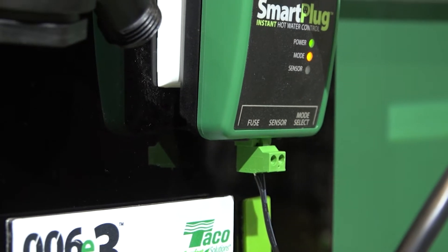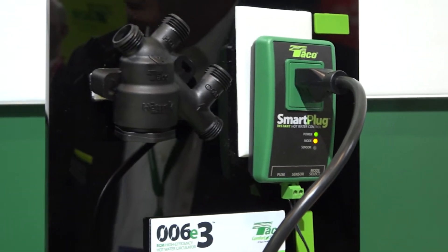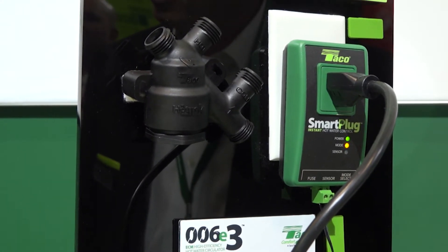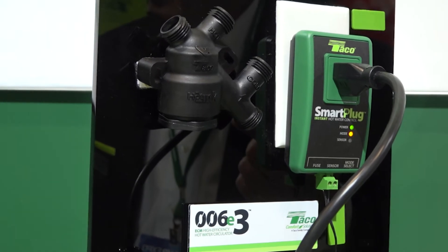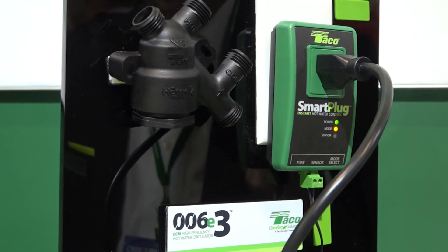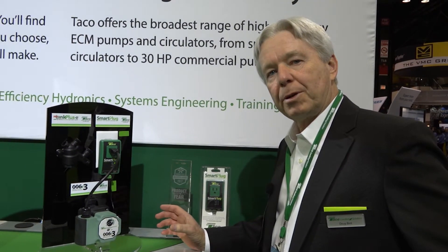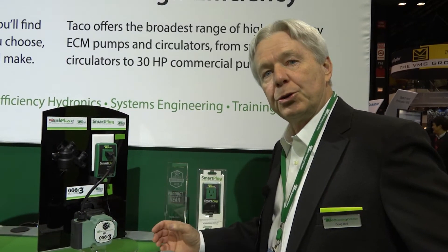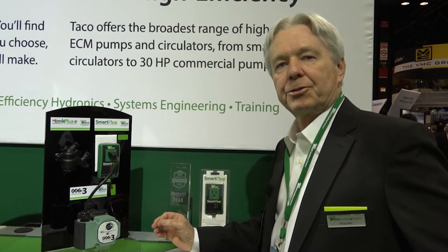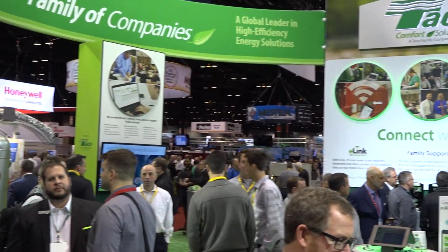Now the mode is set to solid yellow, which tells us it's in learn mode. Through the sensor, it's learning exactly when the homeowner uses hot water in the house, and stores that data over a seven-day period. The following week — Monday, Tuesday, Wednesday, Thursday and so on — it tells the pump exactly when it needs to run. If you'd like to learn more about the SmartPlug E and the Hot Link Plus E, you can visit our YouTube channel where we have instructional videos. Now I'd like to turn it over to Rick Brindamore, who will give you more information on the new valve and leak detection products we have here at the booth.